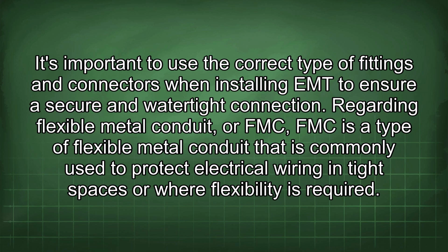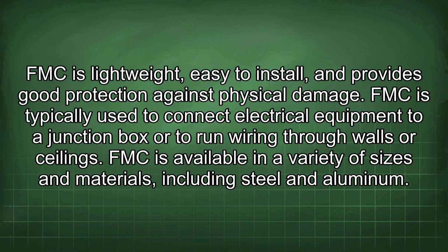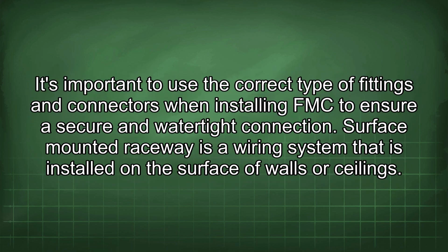connection. Regarding flexible metal conduit, or FMC, FMC is a type of flexible metal conduit that is commonly used to protect electrical wiring in tight spaces or where flexibility is required. FMC is lightweight, easy to install, and provides good protection against physical damage. FMC is typically used to connect electrical equipment to a junction box or to run wiring through walls or ceilings. FMC is available in a variety of sizes and materials, including steel and aluminum.